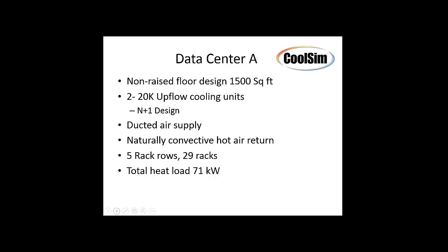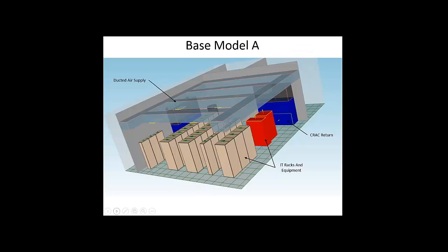I'd like to point out that CFD modeling is not exclusive to only big data centers. It's very helpful in small data centers. In fact, often more helpful in small data centers because you've got less volume and more room and things are swirling around even more vigorously than they might be otherwise. This design is not an air handler in the sense that it's got an outside chiller. So this one is an on-off state. So we're going to shut one of them down and just look at it when it's running under one unit.